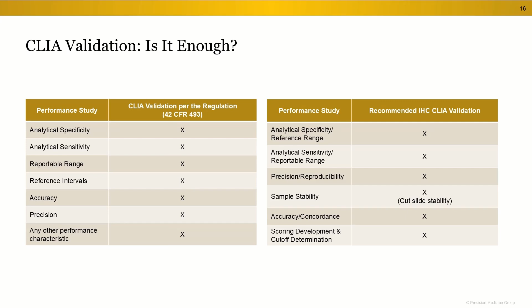And what about, we've talked about the CLIA validation requirements, but what if that's not enough? Right. So when you think about moving past the CLIA validation and adding to what would be required for a pre-market submission, there's another set of studies that are required, as I mentioned earlier, and these are in compliance with the CLSI guidelines. So there's a guideline for theoretically every type of study that would be needed to validate your assay. And it's very prescriptive on replicates, lots, designs, stats. Acceptance criteria is a big one. You need to set your acceptance criteria before you conduct the studies.